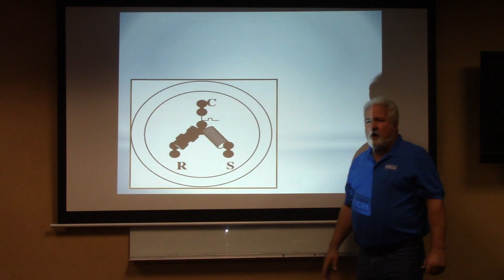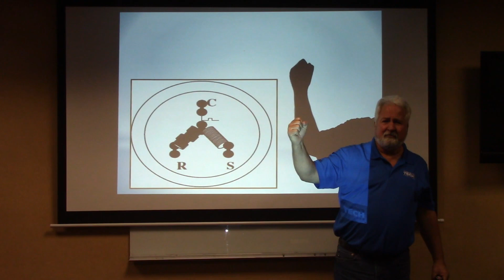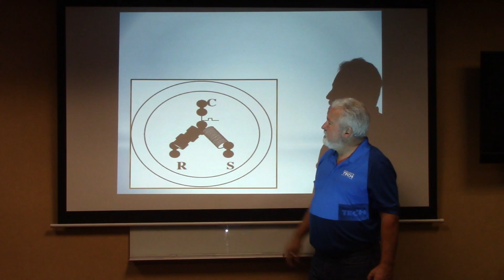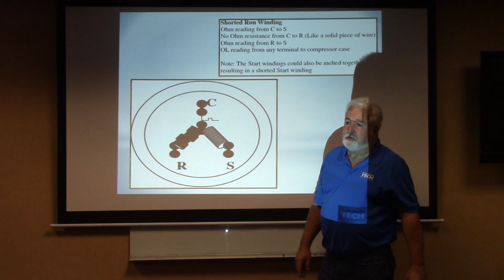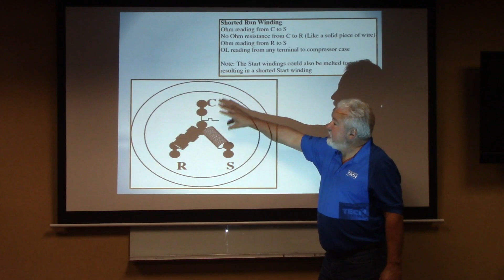What if that entire winding just melted together into one big chunk of copper? It got so hot it all melted together. How much resistance would I have then? Very little resistance. So in that case we'd have a shorted run winding. Would I have an ohm reading from common to start? Yes. From common to run? It might be very minimal, maybe 0 ohms. From run to start? Yes, same thing, because I still have resistance there. From any of these to the case? No, I'd get an OL reading - a lot of ohms. So this would be shorted.